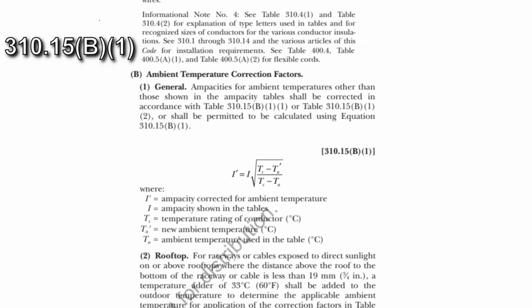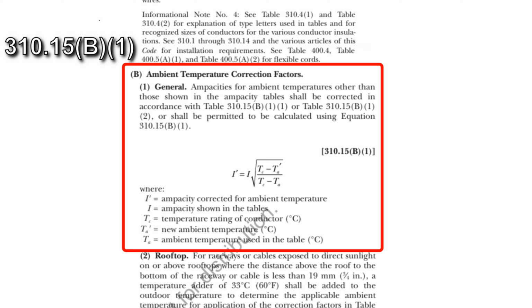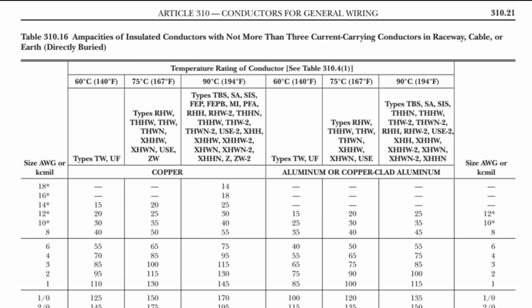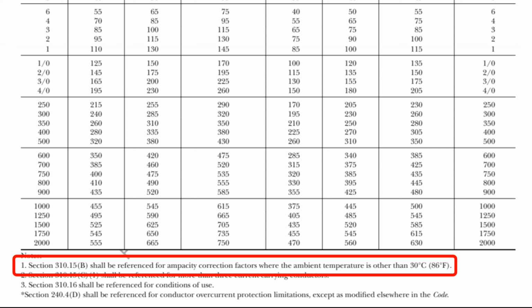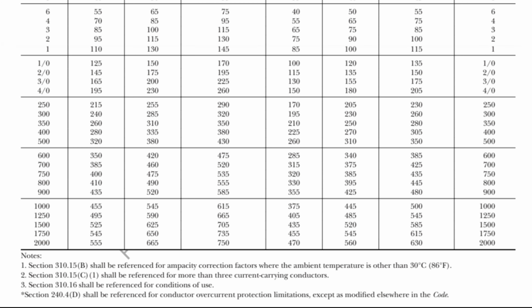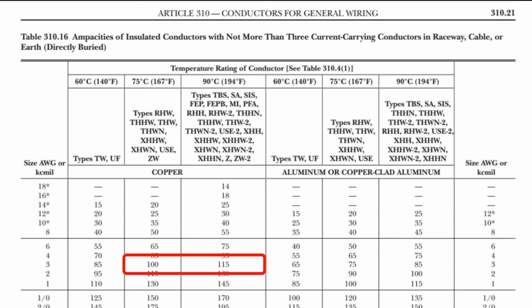Next, 310.15(B)(1) General. Ampacities for ambient temperatures other than those shown in the ampacity tables shall be corrected in accordance with 310.15(B)(1)(1) or Table 310.15(B)(1)(2), or shall be permitted to be calculated using Equation 310.15(B)(1). Let's start by selecting a copper conductor with an ampacity of at least 100 amps. So it looks like maybe a number 3 copper conductor will meet the need. But these ampacities are based on an ambient temperature of 86 degrees Fahrenheit. Now let's look at the possibility of correcting that ampacity due to an ambient temperature of greater than 86 degrees Fahrenheit. So we're starting this process by applying temperature corrections to our conductor ampacity table values.